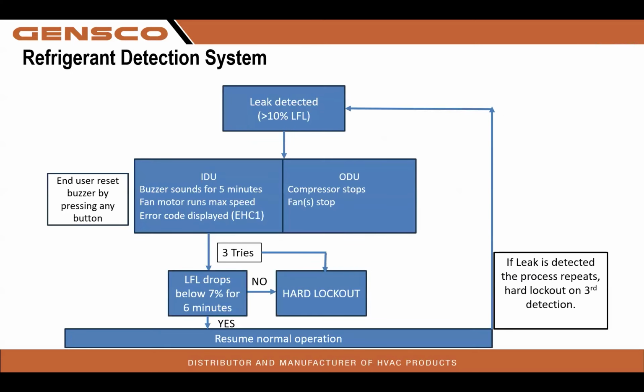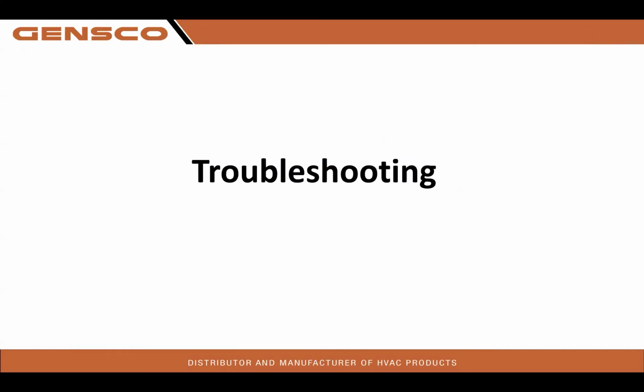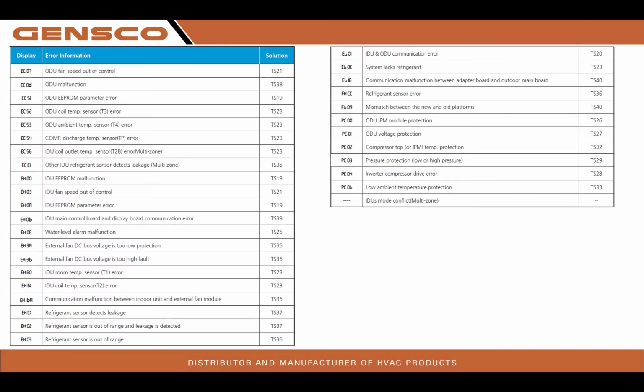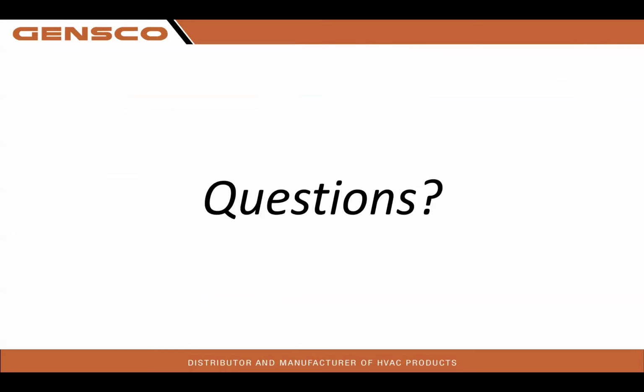We already went through the refrigerant detection system: leak detected, outdoor unit shuts down, fan kicks on, and so forth. If a leak is detected, the process repeats, with a hard lockout on the third detection. Troubleshooting, there are lots of error codes on the inside panel of the air handler and in the cased coil. So on the 7-segment display, look at your error codes and start chasing down what the error code pertains to. All right, questions.